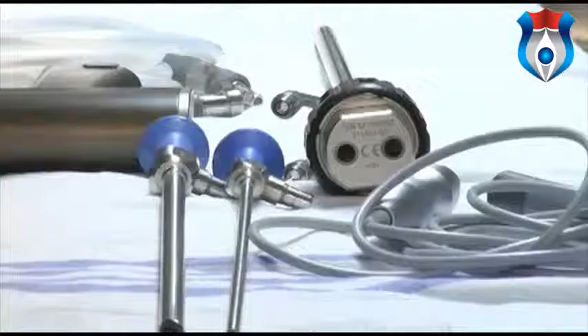In the decontamination area, each cart is broken down with the instrument containers separated from the instrument baskets. They're washed by hand using an enzymatic cleaner to break down blood and protein on the instruments. The technicians wear the proper personal protective equipment for working in decontamination. The instruments are then placed in a washer for a 45-minute wash and dry cycle to further decontaminate the equipment.